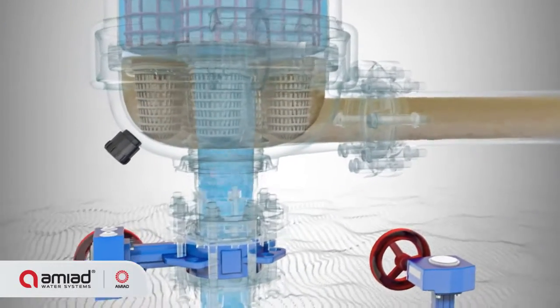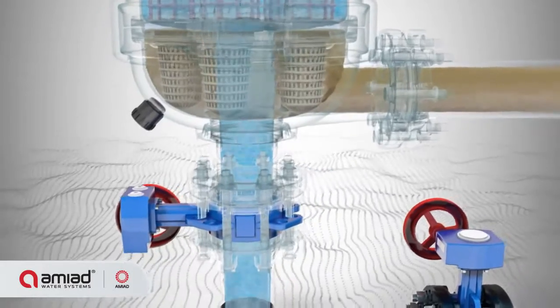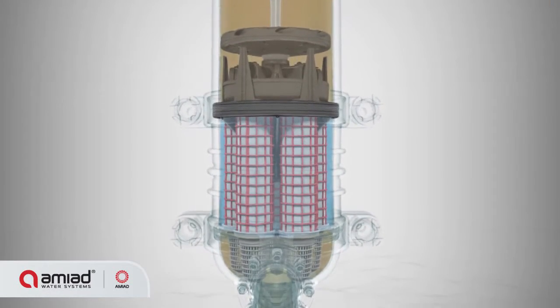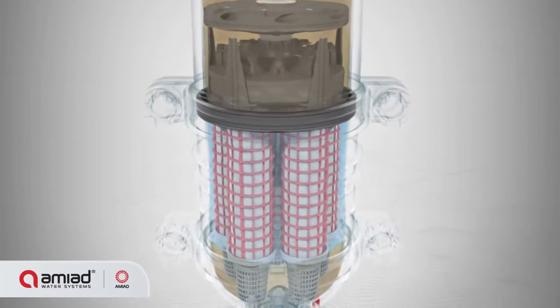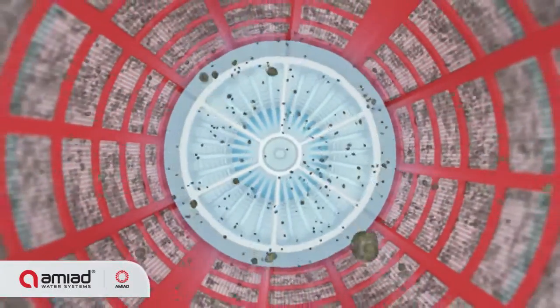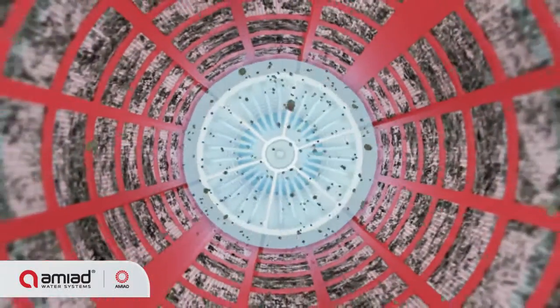The filtration process starts when raw water enters the filter through the inlet and flows to the coarse screens, where the water is pre-filtered to block and remove large dirt particles. The water then passes through the fine screens, trapping dirt particles on their inner surface. Dirt is accumulated within each screen, and clean water flows through the filter's outlet.